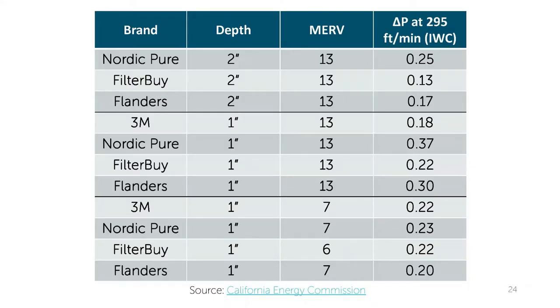Depending on the specific filter, pressure drop can vary, and this can affect the amount of air the fan can move. This gets worse the longer you go between filter changes. Choosing thicker pleated filters can help, but all filters need to be evaluated for system compatibility to avoid excess energy use, comfort issues, cracking heat exchangers, and refrigerant evaporation issues.